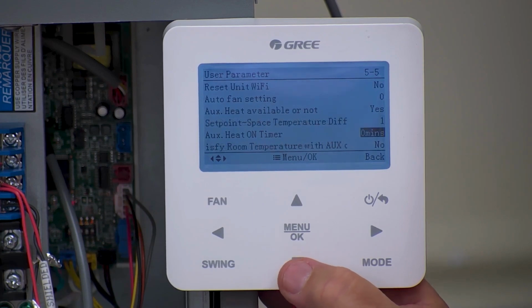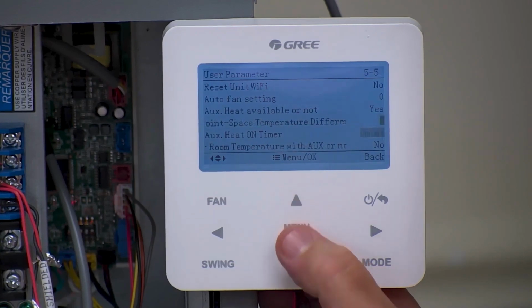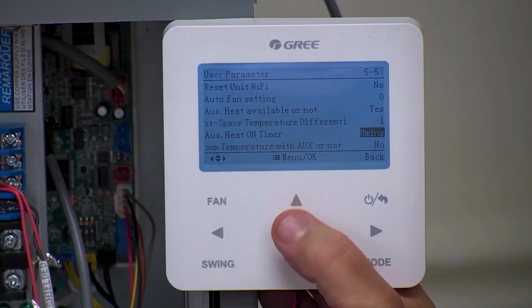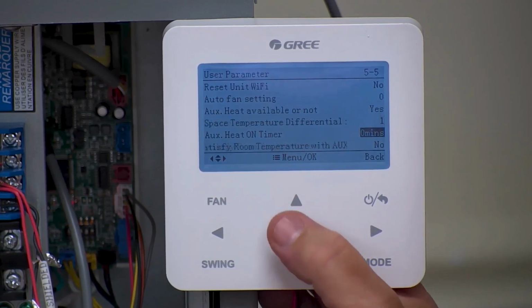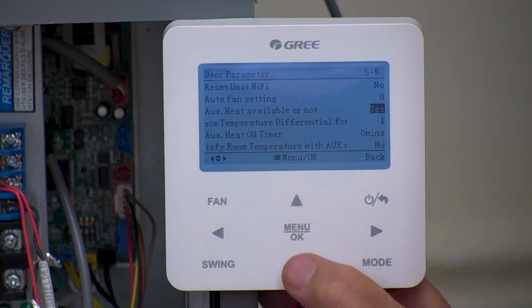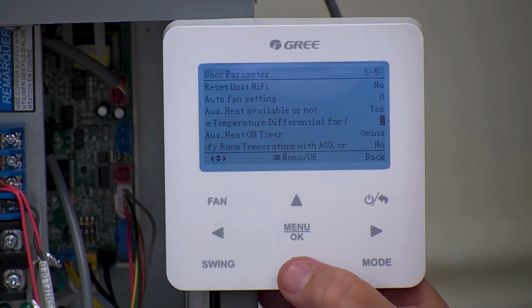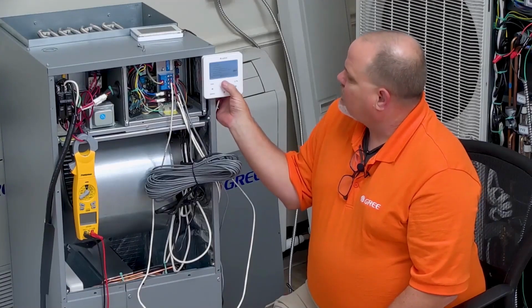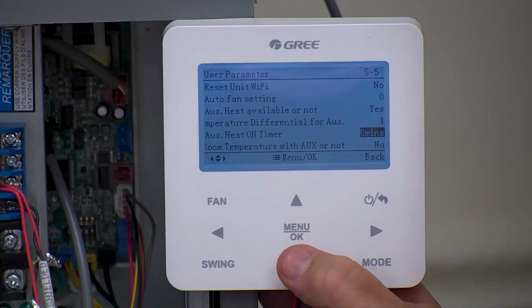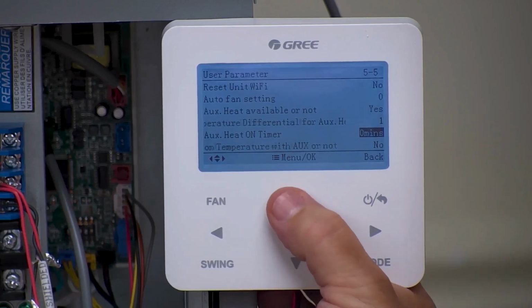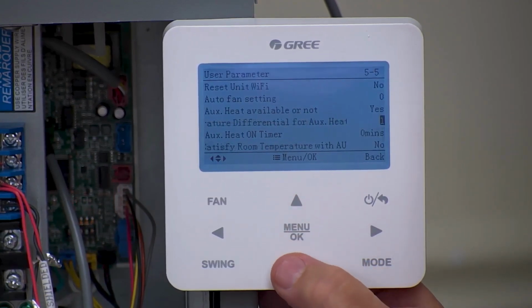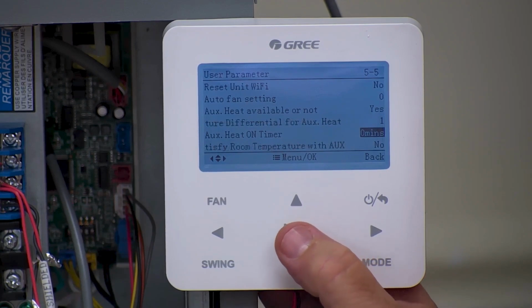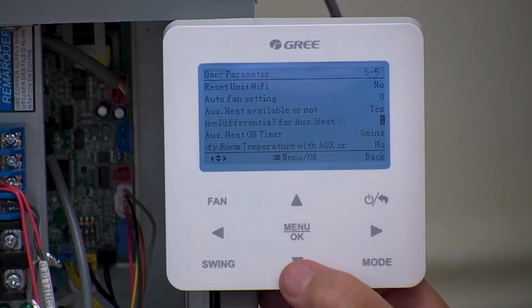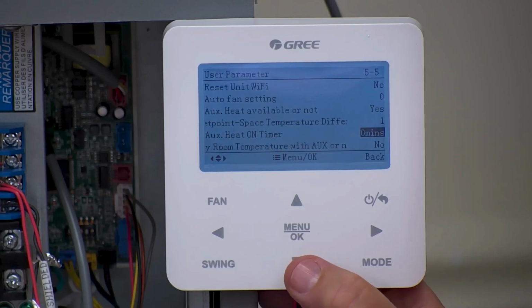As we go down a little further, auxiliary heat on timer, 0 minutes, you can set that from 0 to 60. Meaning, you could actually set this up that, say you got an older person like me, because I am getting old, right? And we inherently like to go to the thermostat and say, I'm cold, and we turn the temperature way up. Well, they're kind of defeating the purpose of having a heat pump, especially if it's 40 degrees outside. So what you can do with that timer is set it to 10 minutes. You can go 0 to 60.